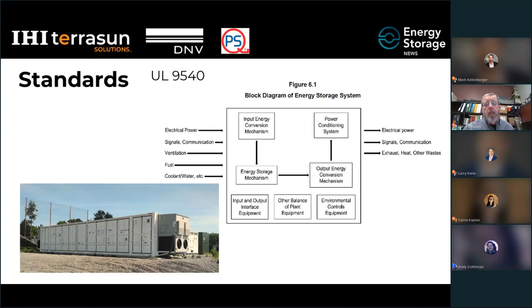The next edition of UL 9540 has a scope change, and a change to figure 6.1. This will make it clear that yes, in fact, you can have an energy storage system that just has the batteries and the controls for the batteries. You don't have to have the converter or the inverter as part of the overall energy storage system, which makes things a little bit easier to address and avoids the overlap of jurisdiction from the authority having jurisdiction and the certification or field evaluation agency.